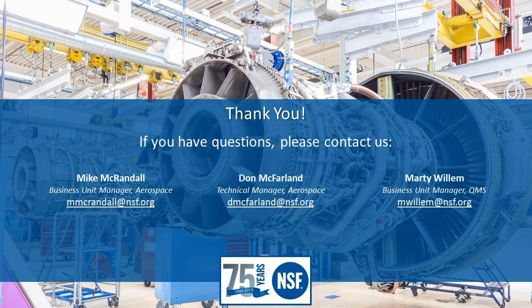It really does depend on the nature of the work, the type of inspection that's been prescribed. If we're simply looking at the material to ensure that we didn't get shorted by the supplier, Don's opinion, no, I don't need a calibration. If I am a distributor and my customer's requirement is that it needs to be a 144-inch bar, and it's coming in and I'm going to confirm it at that point to ensure that it's a 144-inch bar and it's never going to be inspected again, I probably want to have some way of verifying my tape measure.